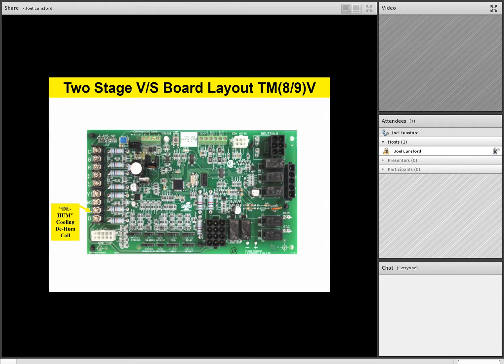The O terminal is for a heat pump, and so this board is heat pump compatible. If you have a dual fuel system or a hybrid system, the O terminal tells the board that the unit is on a heat pump and it's in the cooling mode. Because remember, on our Champion furnaces and our Champion outdoor units, on our heat pumps, the O terminal energizes the reversing valve for cooling mode of operation.